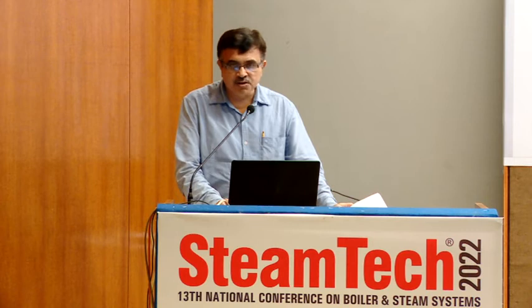Let me start with the drone, and how it can be helpful to the boiler industry. Boiler inspections are mandatory. Every year, all industries have to carry out the maintenance. It is necessary by law, and the insurance company also asks for this inspection. However, some organizations recommend conducting an additional external inspection halfway through the year while the boiler is under pressure. Normally, the boiler is required to be at zero pressure to do the maintenance and the inspection work.